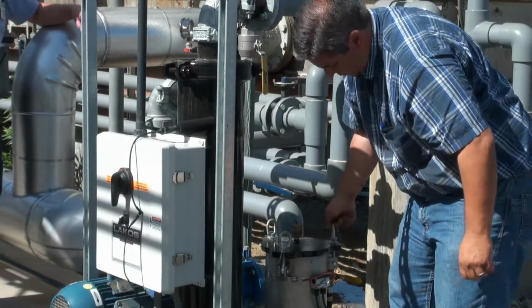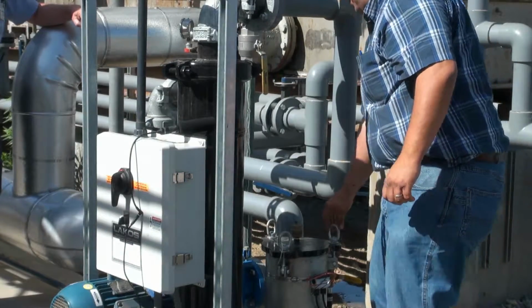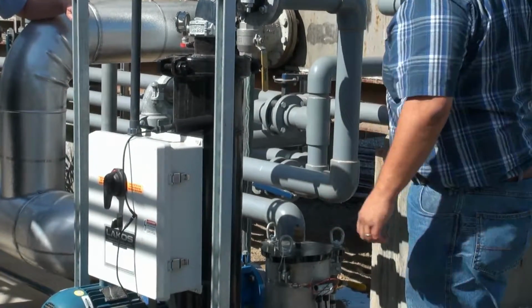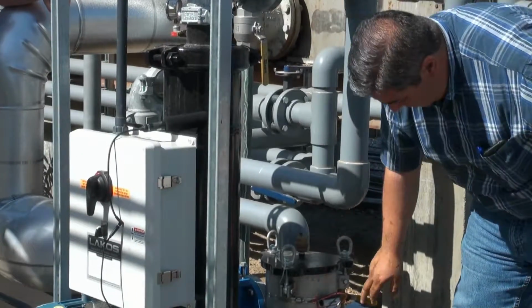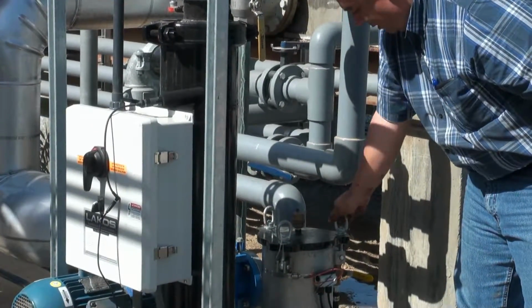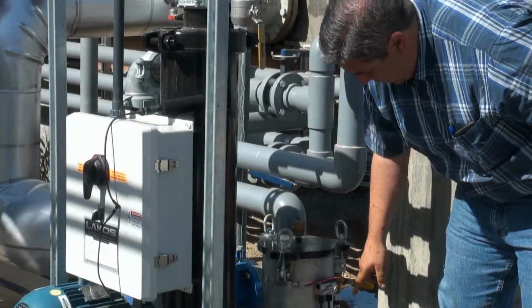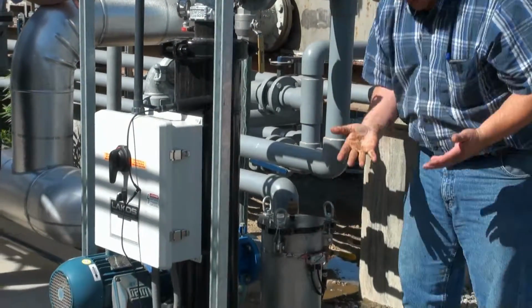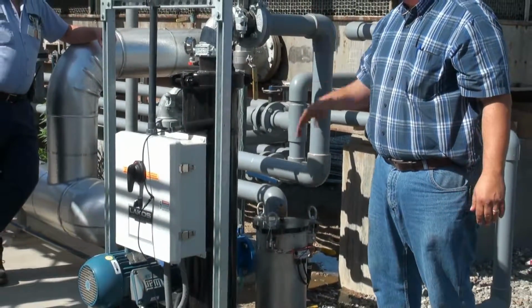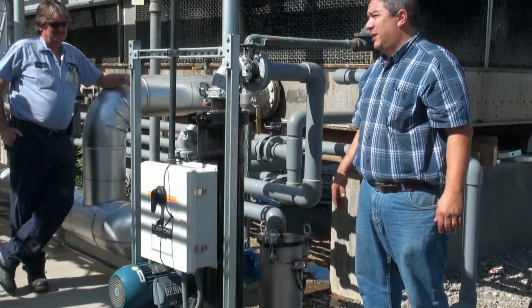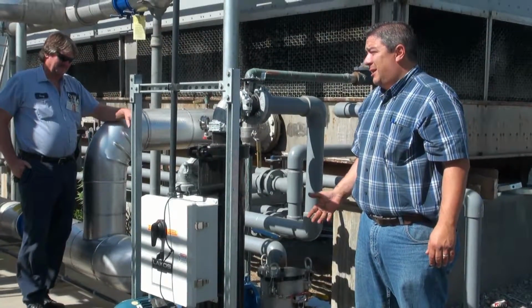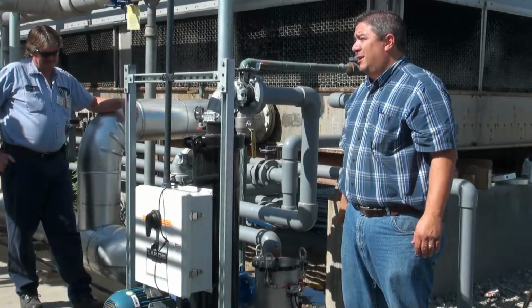So that pressure gauge didn't work. Yeah, we're gonna look at that now. There's a pressure gauge right here that tells you when the bag is empty or full. It depends on this tubing, because the grime gets into that sensor and it'll blow it all the time. So don't depend on that being a good sensor for a long period of time, it's just not a complicated sensor to handle what's going on.